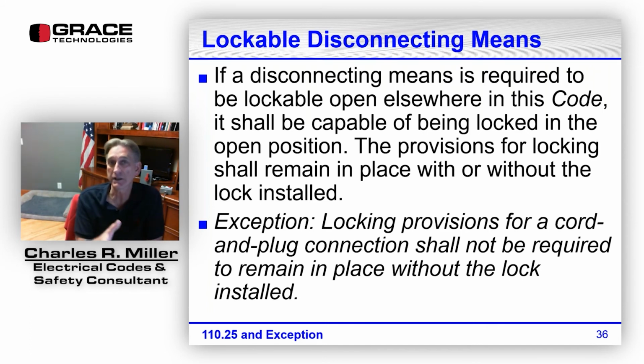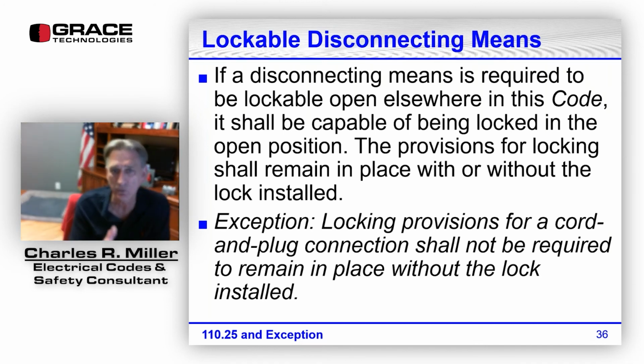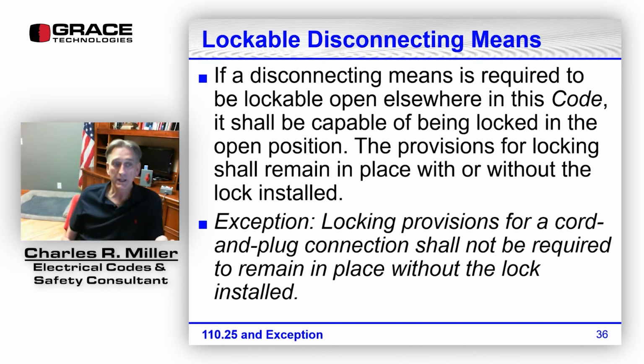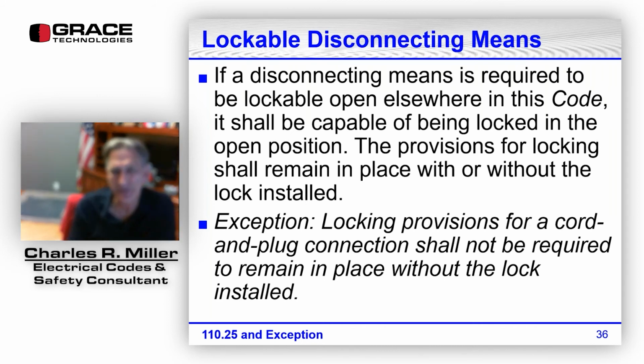So the section in Article 430 for a long time always gave the exact instructions, where the exception was under the requirement for having a disconnecting means within sight of the motor. Then this section was moved to 110.25, and now Article 430 references this, which I'll give you an example of coming up here. There's an exception for this: the locking provision for cord and plug connection isn't required to remain in place without the lock installed. All right, so let's look back and see what this really means above.